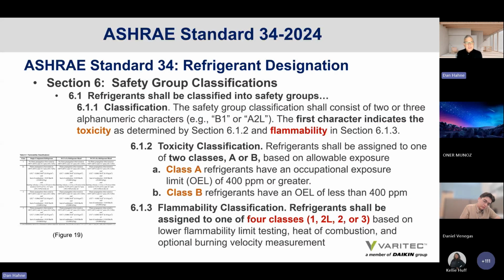Standard 34 also, in section 6, provides safety group classifications. So in 6.1.1, the classification of refrigerants, the safety group classification, it states that the safety group classification shall consist of 2 or 3 alphanumeric characters. The first character indicates the toxicity as determined in section 6.1.2, and flammability in section 6.1.3. Under 6.1.2, the toxicity classification is Class A for refrigerants that have an occupational exposure limit of 400 parts per million or greater, and classification B has to do with refrigerants that have an OEL of less than 400 parts per million.